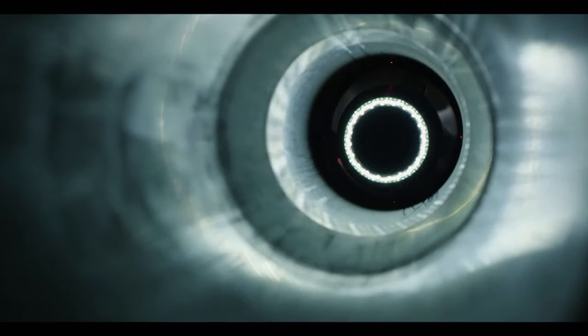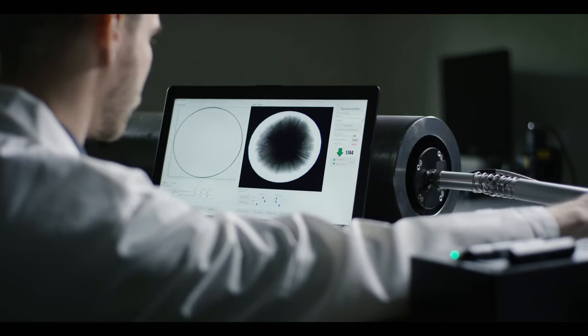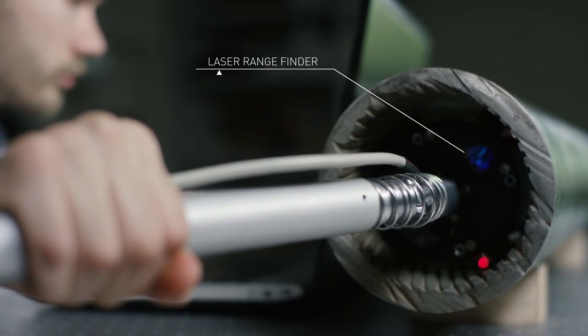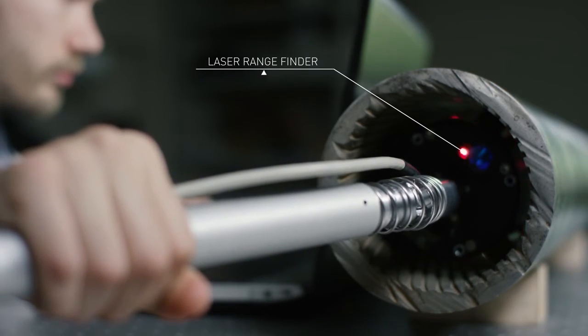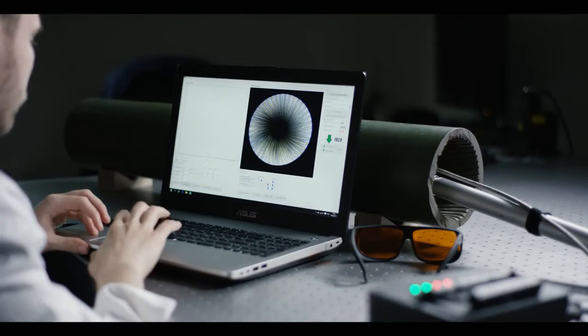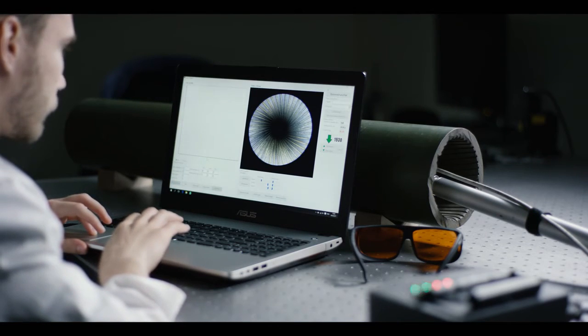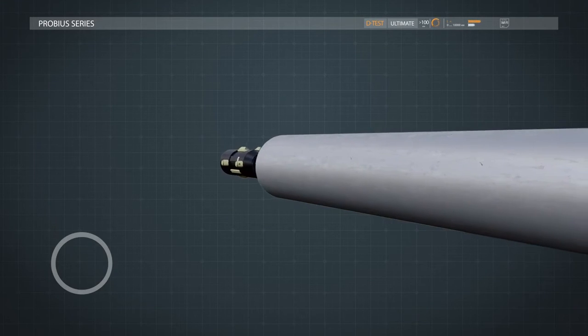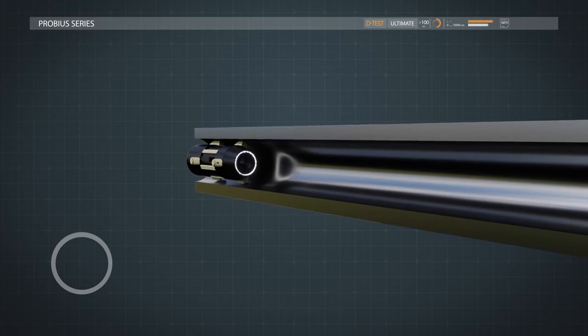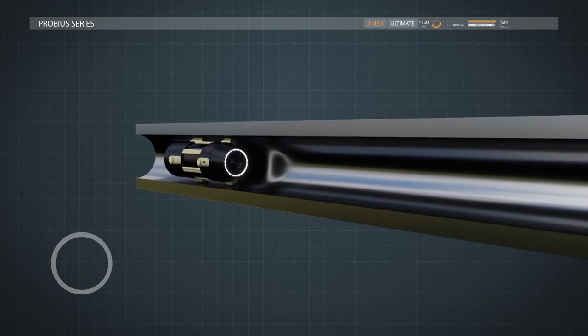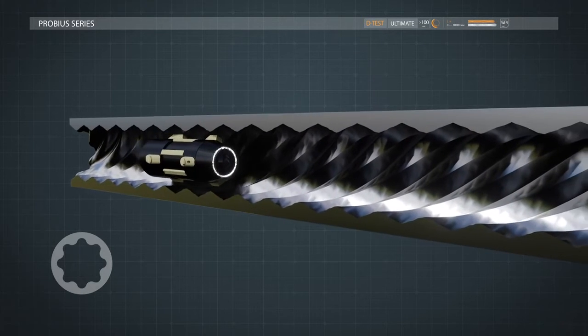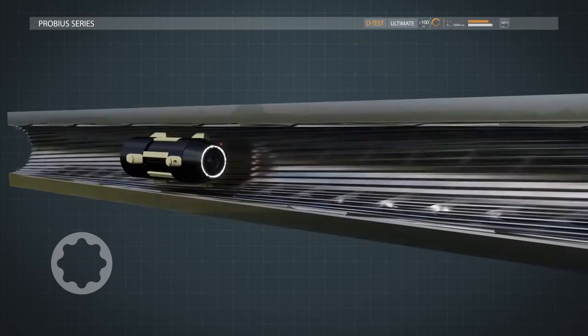The frontal camera helps to find a defect visually, and the laser range finder detects its exact location inside an object. You can study a defect with a laser scanner and take a detailed panoramic picture. ProBius can be moved manually or automatically inside cylindrical objects of simple and complex shapes and simultaneously perform a whole range of measurements.